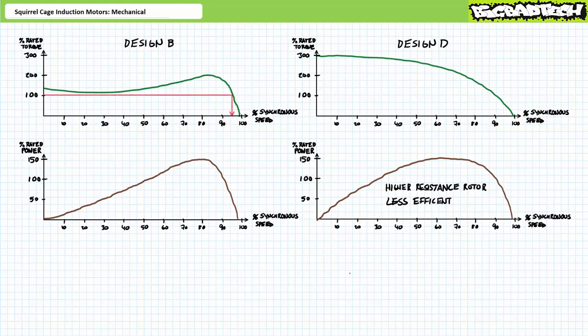A design B motor is expected to produce 100% of its rated torque at 1 to 5-ish% slip, depending on size and manufacturer. Assuming 3% slip, this means 100% rated torque occurs at 97% of synchronous speed. Design B motors ordinarily experience a peak breakdown torque around 200% of its rated torque, somewhere around 80-ish% of synchronous speed.